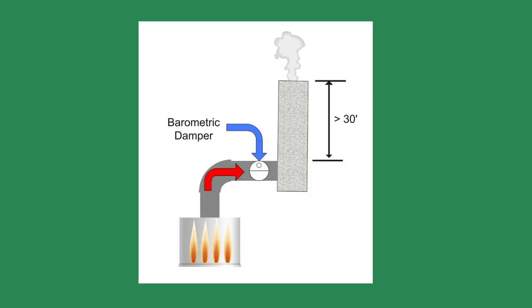A barometric damper is used for just its purpose. It is set for the proper boiler draft, and if the draft is higher than the setting, it will open and allow boiler room air into the chimney. This keeps the flame stable and lowers the heat lost up the chimney.